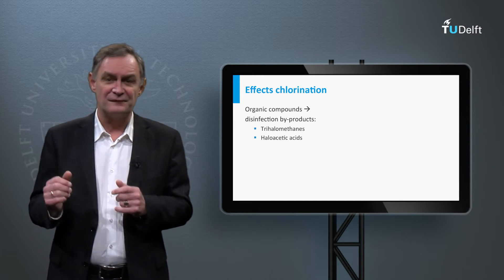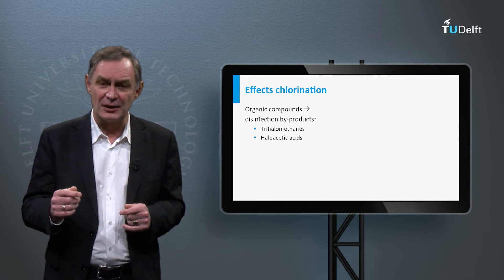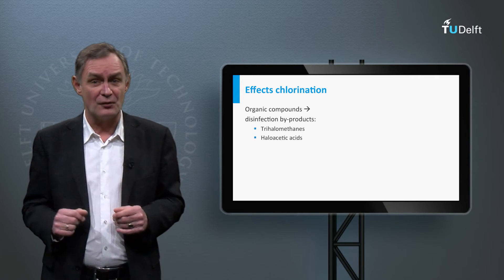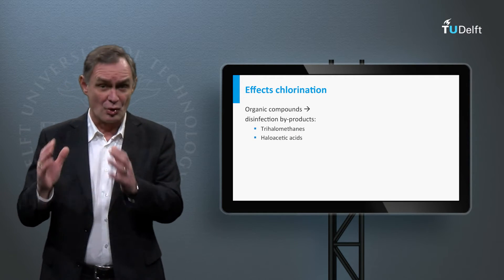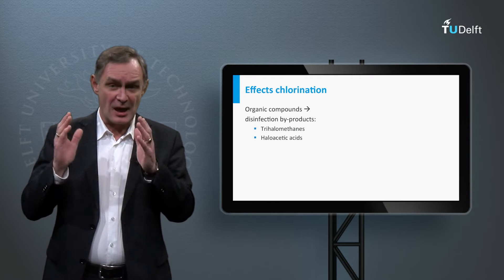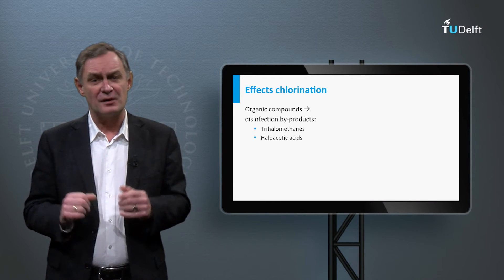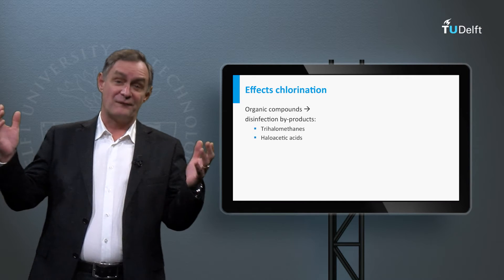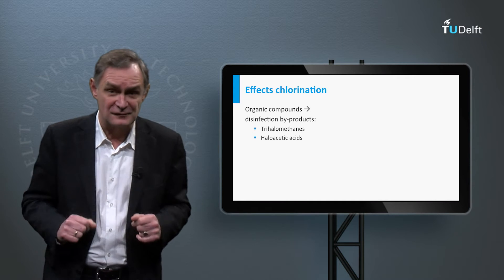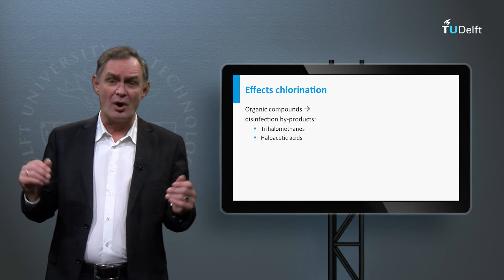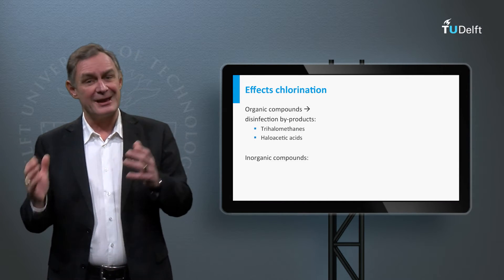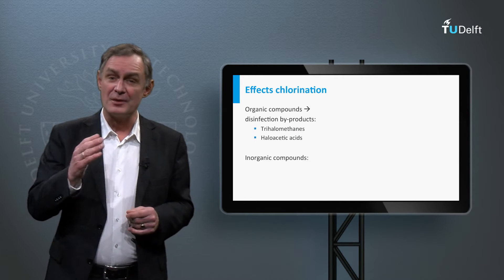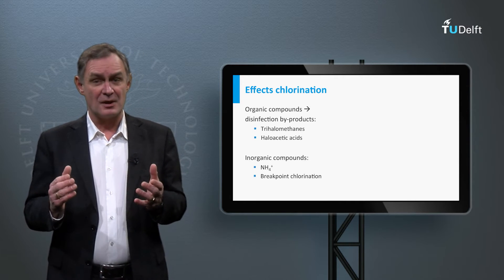The disinfection by-products can be avoided by removing the natural organic matter from the water, for example by coagulation, activated carbon filtration, or ion exchange, or by avoiding high dosages. Furthermore, chlorine can react with inorganic compounds. Ammonium can be removed by chlorination.